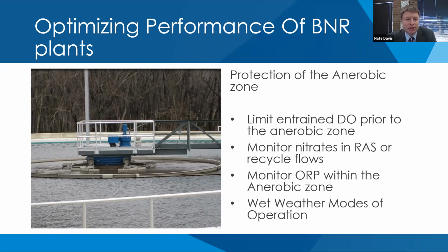I've touched on this a little bit. It is actually protecting the anaerobic zone: limit DO, monitor nitrates in your RAS and recycle flows, and keep an eye on that ORP. Also, in designing plants, I like to put in wet weather modes of operation where we can divert excess wet weather around the anaerobic tank to protect the integrity of that zone.